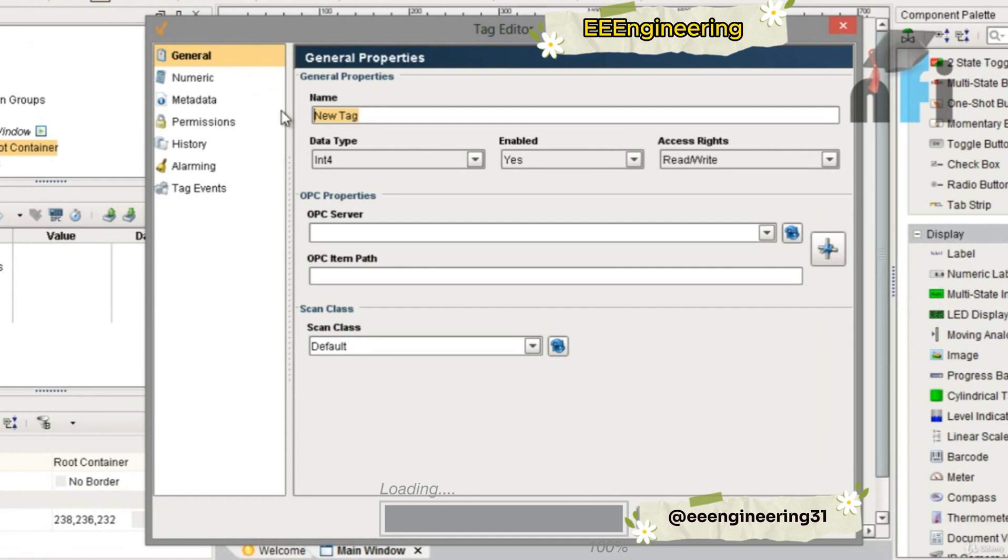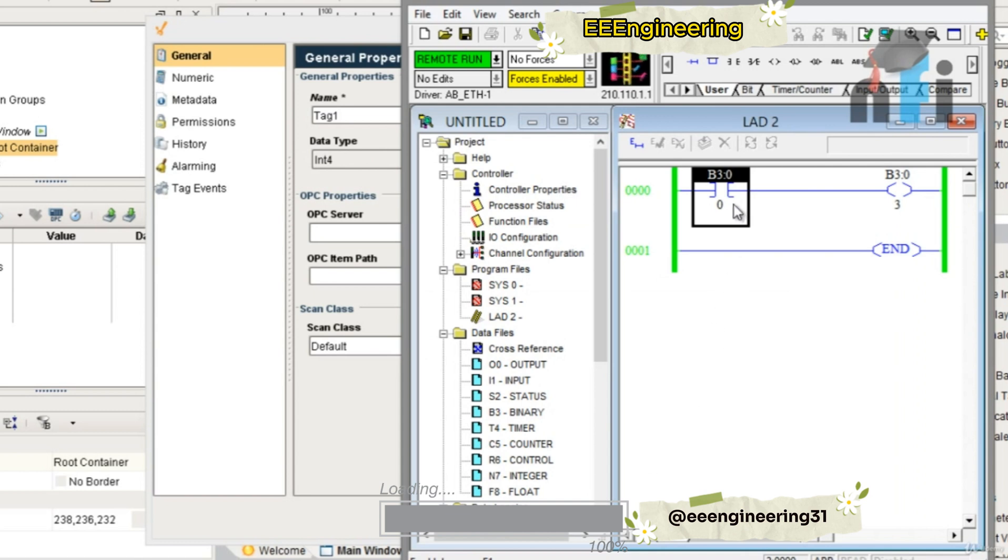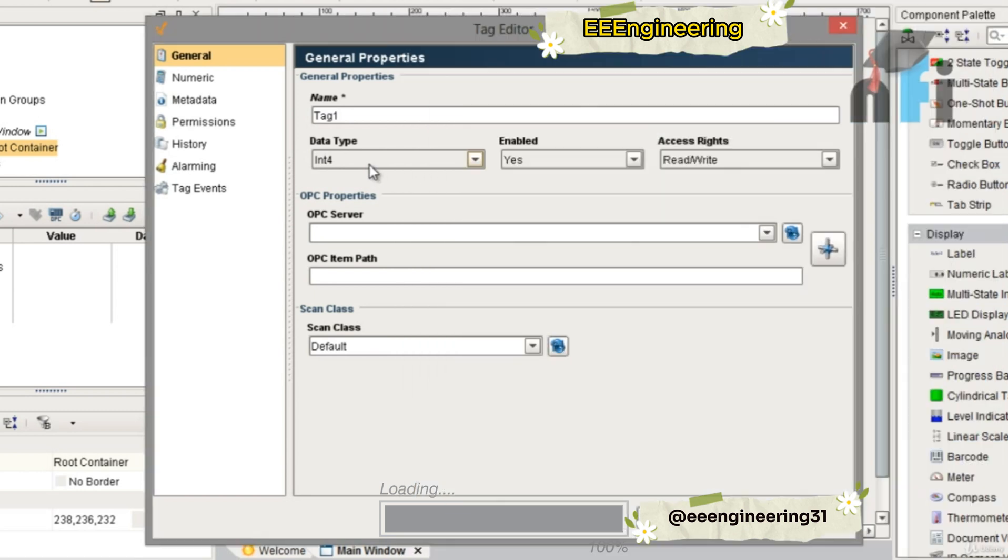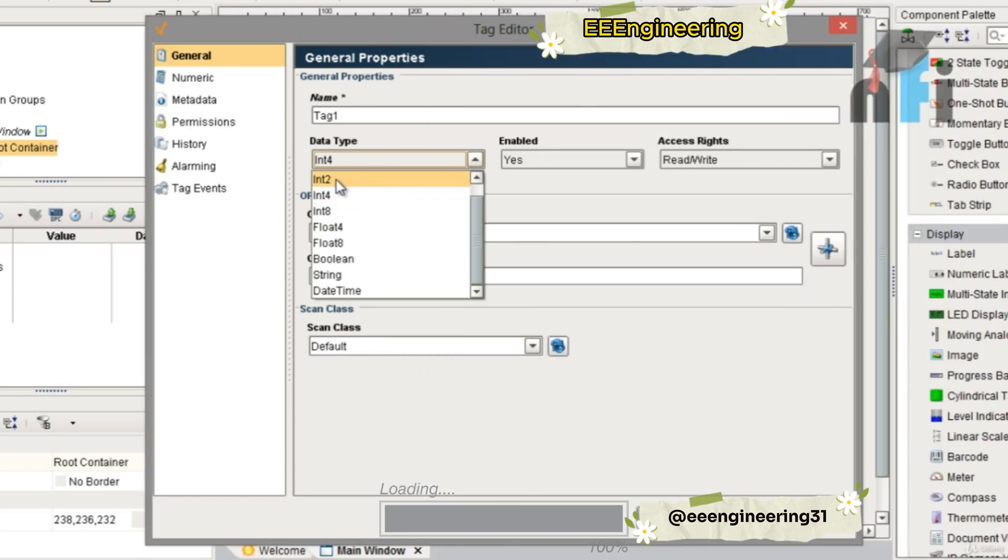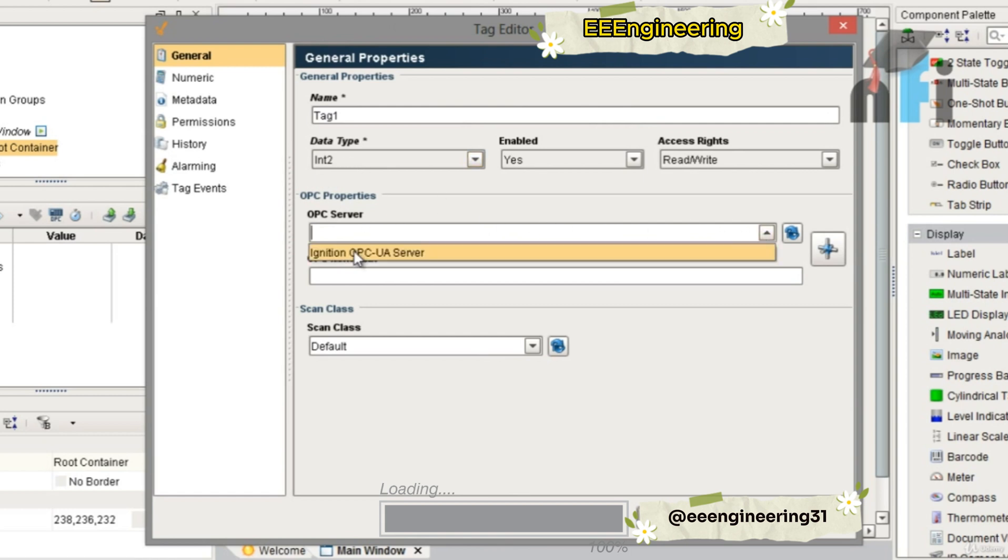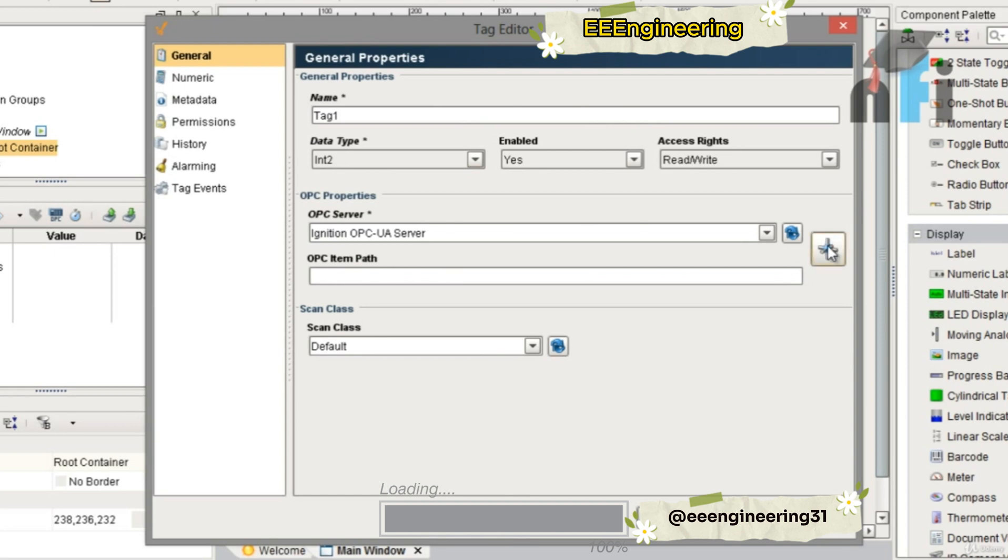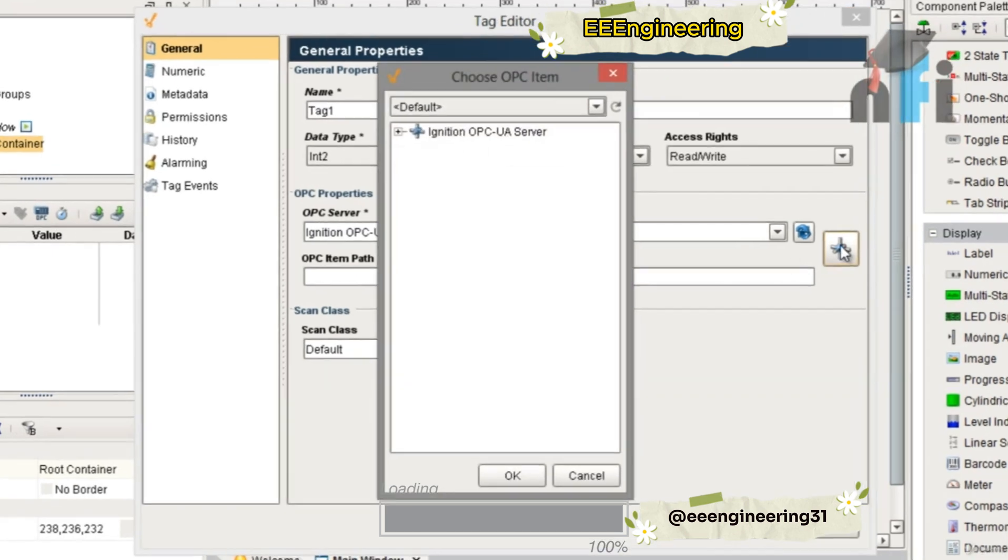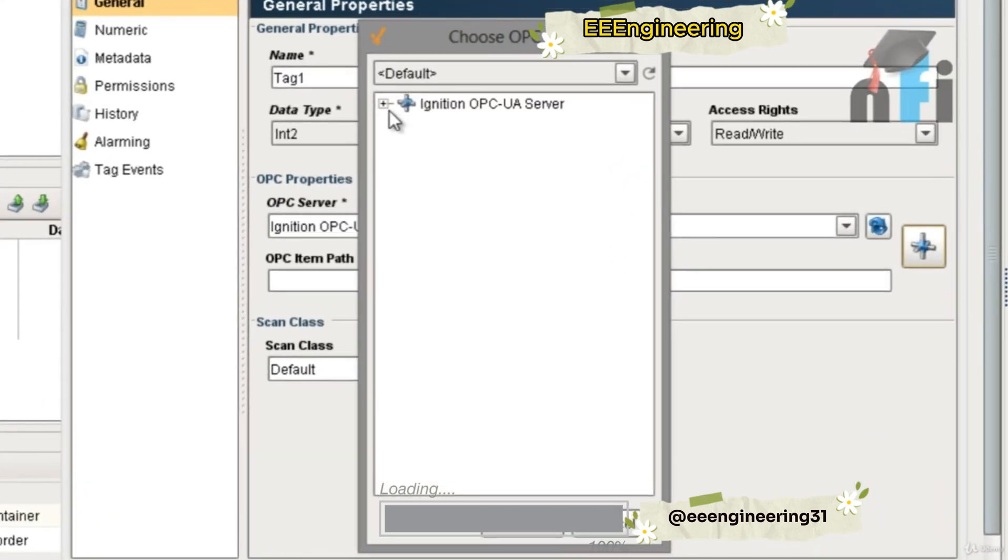You can name your tag, let's say tag1, an int type. Now this is a bit, an on/off bit, so in this case you can take int2 for the on/off type. The server you have to select is Ignition server. For item path, you can do this by clicking on this button.